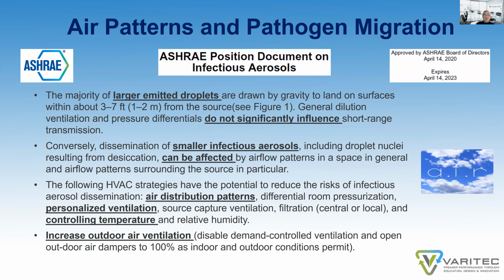Conversely, dissemination of smaller infectious aerosols, including droplet nuclei resulting from desiccation, can be affected by airflow patterns in a space in general and airflow patterns surrounding the source in particular. The following HVAC strategies have the potential to reduce the risk of infectious aerosol dissemination: air distribution patterns, differential room pressurization, personal ventilation. And I want you to take note of air distribution patterns and personalized ventilation because they are applicable to underfloor air systems.